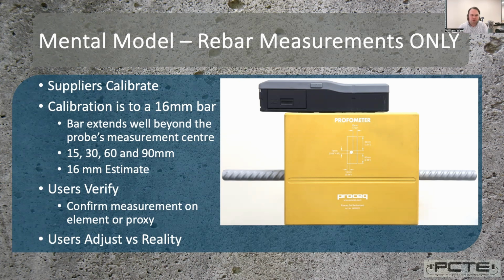So measurements on this test block are 15, 30, 60, and 90 millimeters to a 16 mil bar. And that bar has a couple of key properties because cover meters effectively assume the length of the reinforcing bar is infinite. Now, there's no such thing as an infinite reinforcing bar. So we have a bar that extends well ahead and well behind the cover meter. The cover meter is lined up directly on top of that bar and parallel to it. And then the measurement is confirmed.